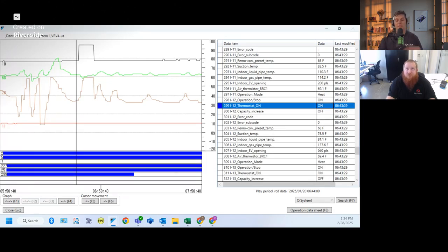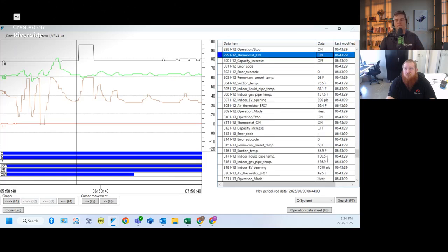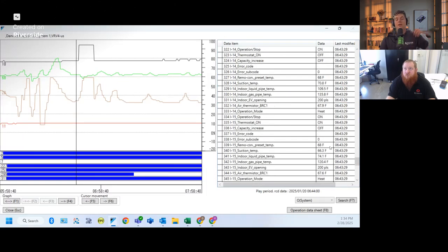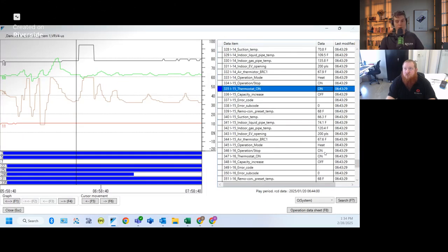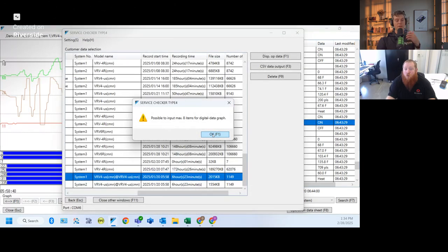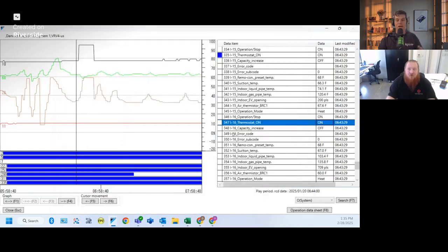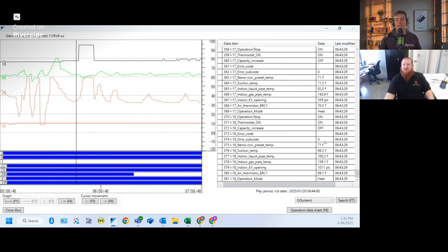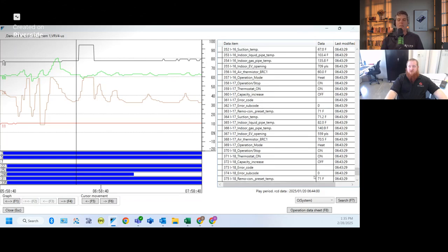That comes back to that other problem where people complain about heat in the space, because if the fan coil is oversized, this 200 pulses keeps the coil hot. The factory setting for most all indoor units from Daikin is low fan speed after satisfied. So if it goes to low fan speed and the coil is allowing hot gas to go through in a small trickle, over time it might actually overheat the space. The way you fix that is change field settings, turn the fan to off when it's thermally satisfied. Then you won't have to worry about blowing hot air in the space or overheating it.